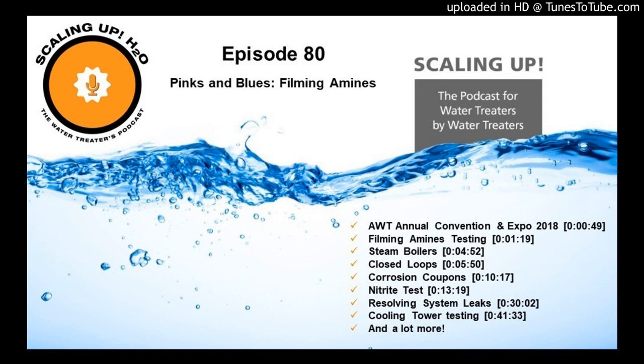Now, most of the systems that I have heard that have had issues were pretty neglected systems, and the filming amine was used very fast when they were putting it in. So I think what happened, and I know this is different case by case, but the cases that I have heard of, it sounds like those systems were cleaned too quickly, and that created a problem because all that gunk, and yes, gunk is a water treatment correct term, was liberated from the entire system, and then it had no place to go, and that's normally where it clogged something up or created some sort of problem. So if that was your issue, perhaps you used too much filming amine too fast.